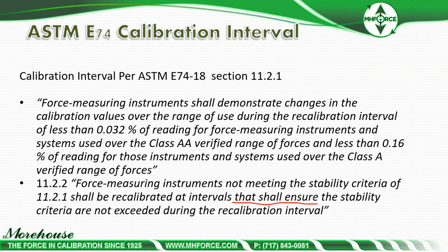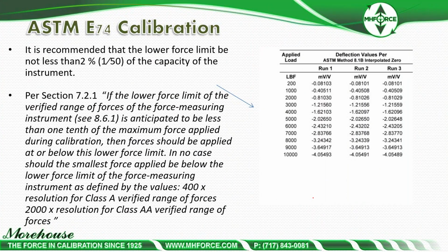So basically what the standard says is, if you meet this criteria, you can have a 2-year recalibration interval. If you do not meet this criteria, you have to shorten the interval so that you meet it. Lots of people will shorten it to a year. Maybe you'll meet at 14 months. Maybe a year is too long. Maybe it's 6 months. So the standard puts it back on you to ensure that you're going to meet it. So there is a judgment call here. We see lots of people that if it doesn't meet, they go to a year, then it meets, then it goes to 2, then at 2 it doesn't meet, then they go back to a year. We see that happen quite a bit.